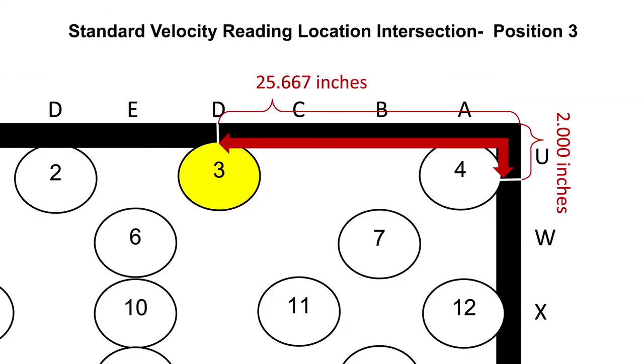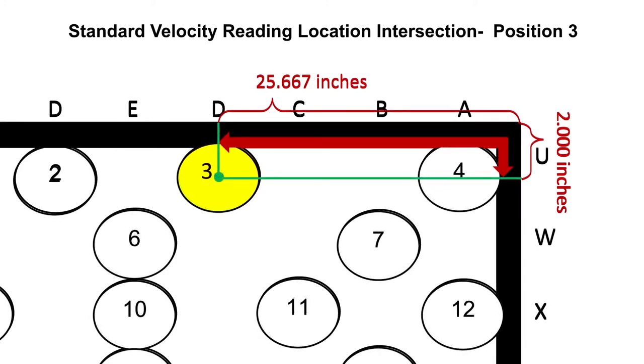Since position 3 is right of the center, it is measured from the right towards the center. Position 3 is at the intersection of D and U. A measurement and marking for D is 25.667 inches from the right toward the center horizontally, and for U, 2 inches from the top towards the bottom. Therefore, the position 3 standard velocity reading location is at the intersection of D, 25.667 inches from the right to center, and U, 2 inches from top to bottom.